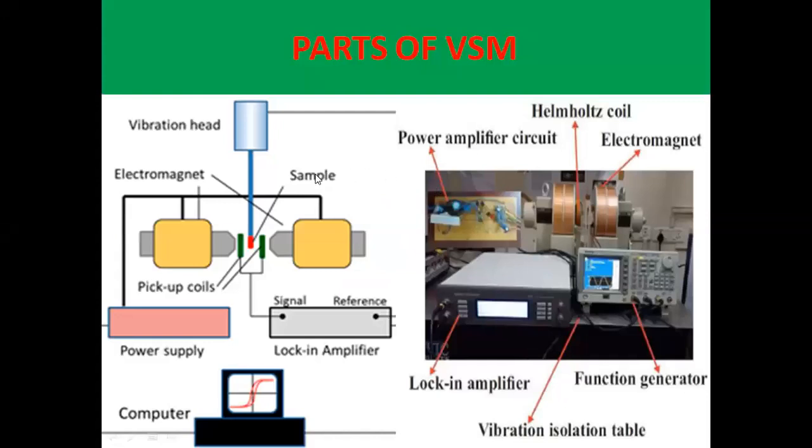Next is the diagram we have. This is the part of VSM. This is the vibration head. This yellow color is the electromagnet. This is the sample which is present in the sample holder. These green colors are pickup coils. We have power supply, lock-in amplifier, and the computer system.